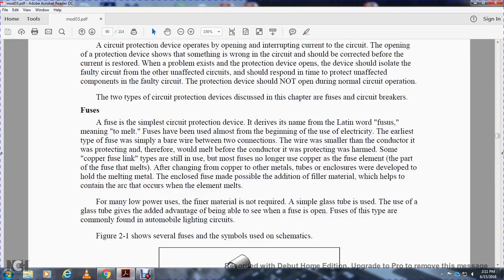All right, fuses. The circuit protective device derived its name from the Latin word 'fusus,' meaning to melt. Fuses have been used almost from the beginning of electricity. The early types of fuses were simply bare wire connected between two connections. The wire was smaller than the conductor it was protecting; therefore it would melt before the conductor it was protecting was harmed. Some copper fuse link types are still in use. Most fuses no longer use copper for the fuse element - the part of the fuse that melts. The material changed from copper to other metals, and tube enclosures were developed to hold the melting metal. These enclosed fuses made possible the addition of filler material, which helped to contain the arc when the element melts.